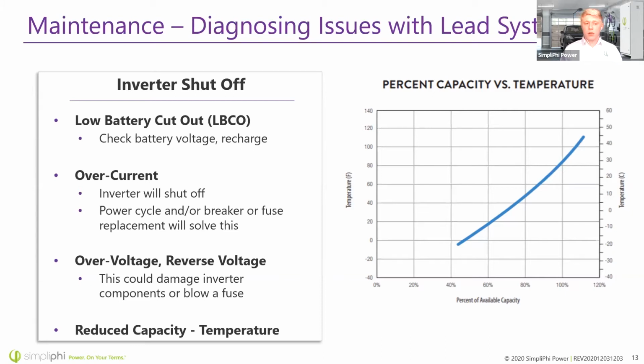Depends on the inverter. And if your inverter shuts off due to low battery cutout, you might be experiencing reduced capacity because of low temperatures. So let's imagine you're at freezing point, at 32 degrees Fahrenheit. Right around here, you've got about 70% of your battery capacity remaining. So if you've hit low battery cutout, you're thinking you didn't use that much energy, check the temperature. That could be an issue.